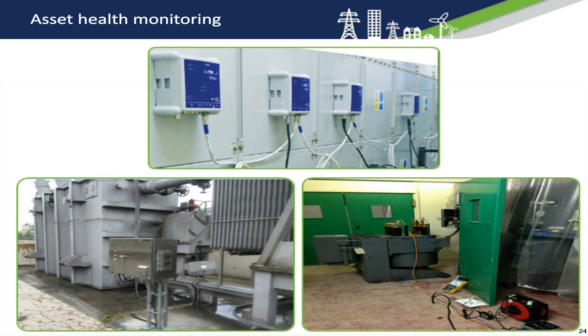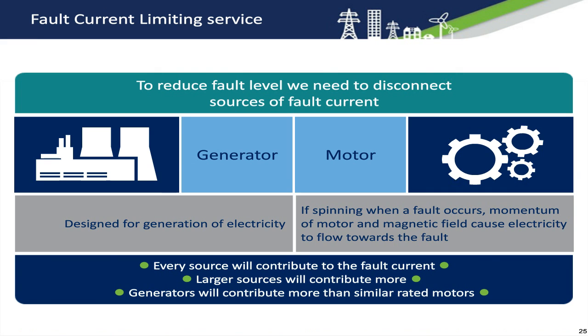The third technique I'd like to go on to is the fault current limit service. Fault current can be generated from a number of sources, including customer equipment running in synchronization with our network. The largest of these are rotating plants, either designed to generate electricity or large synchronous motors that usually consume electricity, but in a fault condition can easily flip into being a generator when the supply voltage drops. These rotating machines can supply up to 8 times their load current at the time of a fault.